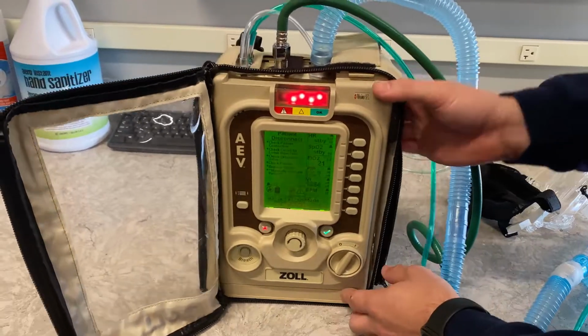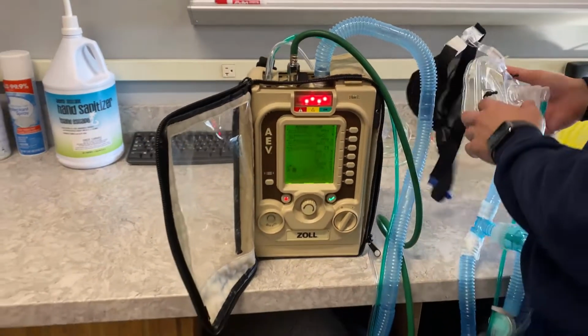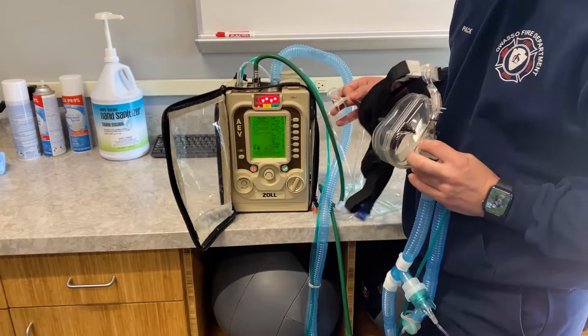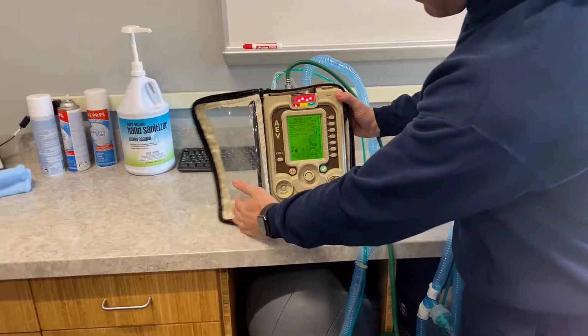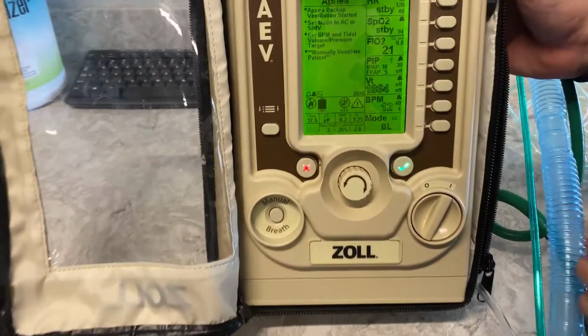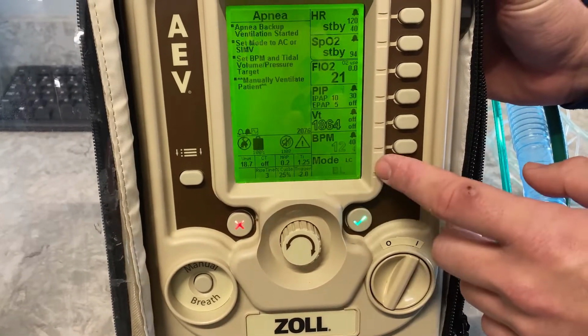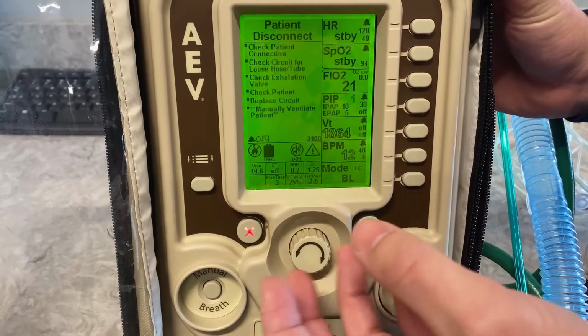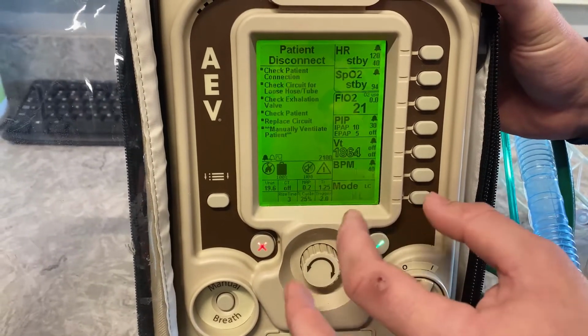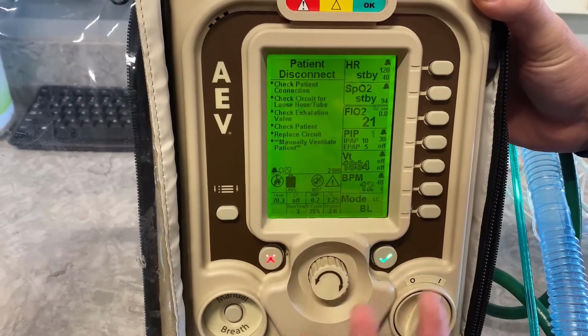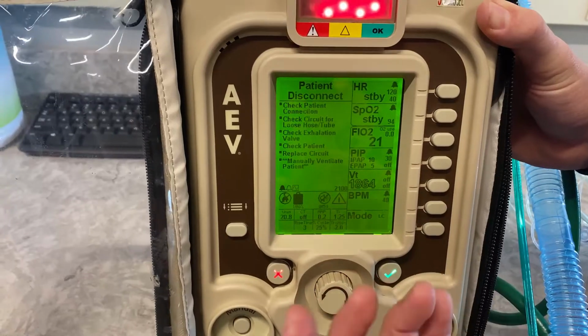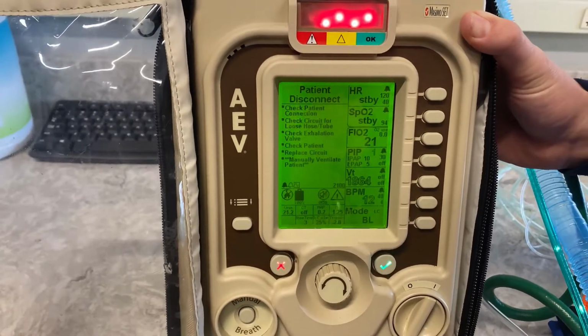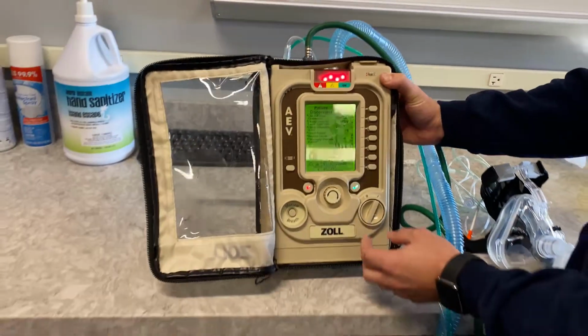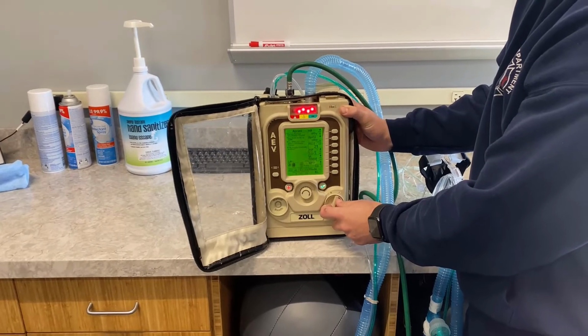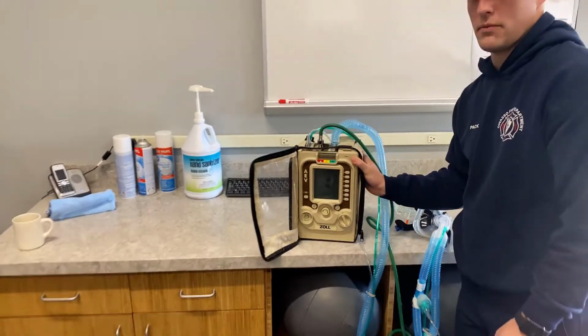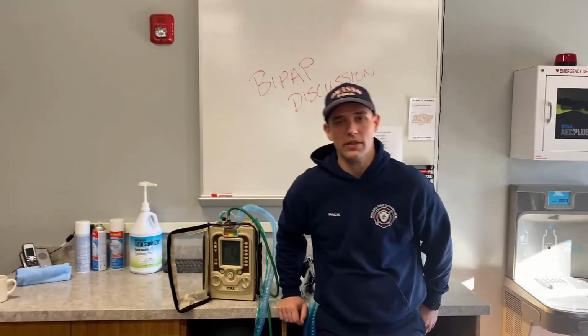Then I just start watching. You're going to get a leak alarm sometimes from your capnography. This setup right here has the leak compensator on, so you will see whenever it is giving a breath that it's going over 1,000. They're getting the adequate amount of air they need, but it's just compensating for the leak. Occasionally you'll see where it doesn't have a leak and it's like 300. Cool. Anything else? That's where I go. That's my go-to. It's super simple, super easy.